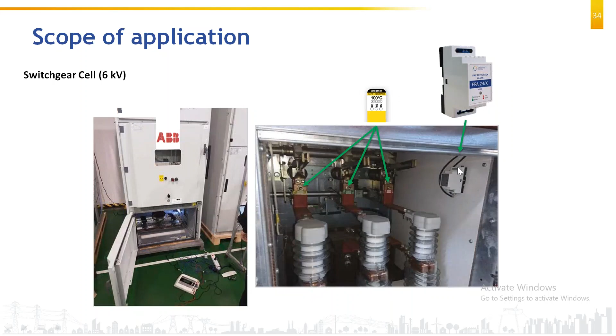Then an example of an 11 kV switchgear panel: we have the incoming chamber, bus bar compartment, metering cabinet, and circuit breaker cabinet. In each cabinet we will install the sensors. You can see all these black parts are the sensors. These three sensors are connected to the FPA. This is a multi-channel FPA which can accommodate up to 4 sensors. The FPA communicates to a remote PC. And this is how it looks inside the panel when it is installed on the bus bar. So this is for the 11 kV switchgear panel.